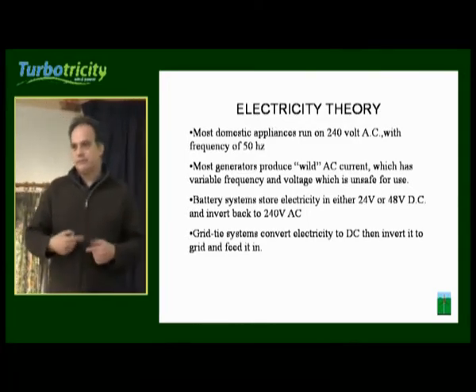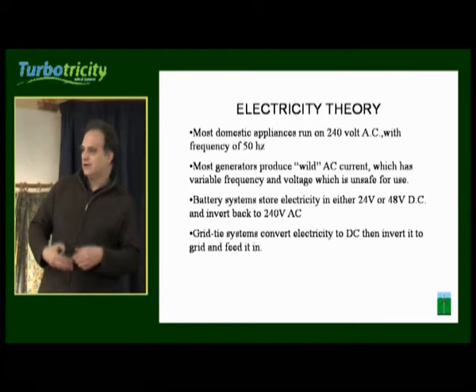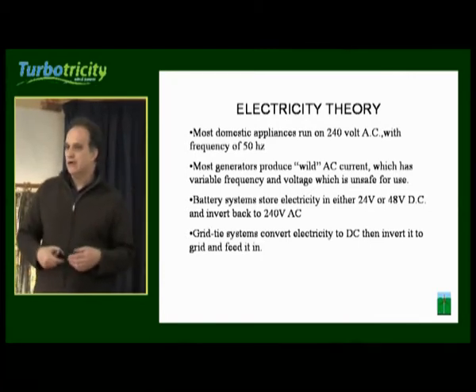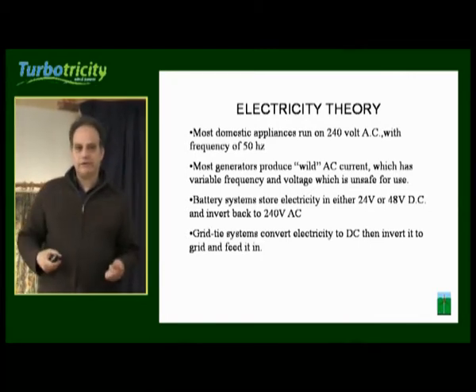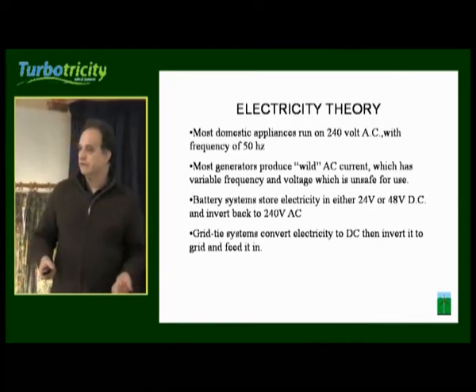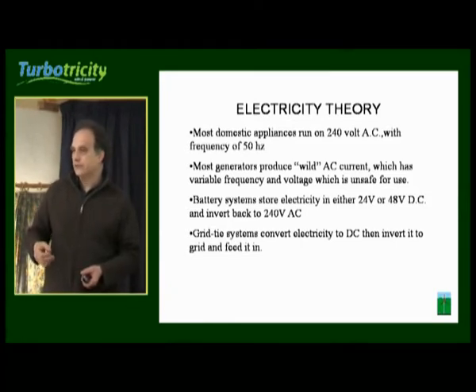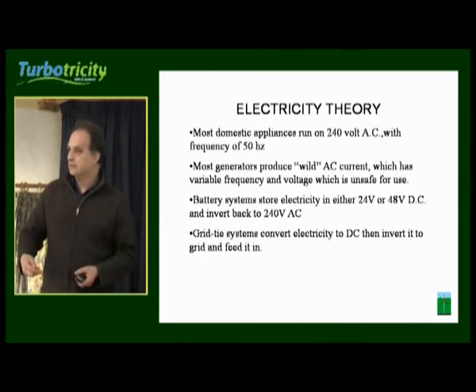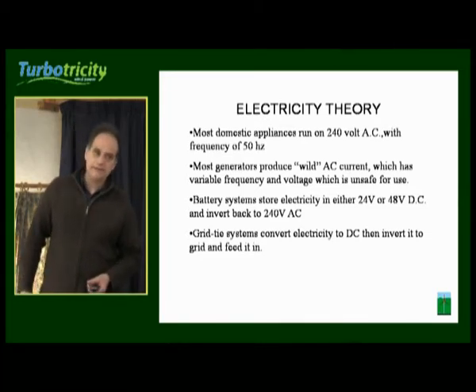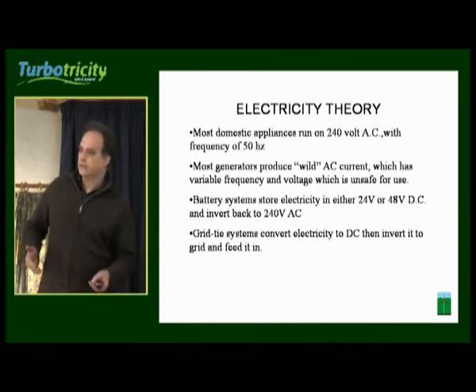Generators spinning around on top of your wind turbine are spinning at various rates, so the frequency is completely variable depending on how fast it's turning. It's also producing variable voltage depending on the speed at which it's turning and the load on it. This kind of electricity that comes off a generator is known as wild alternating current.